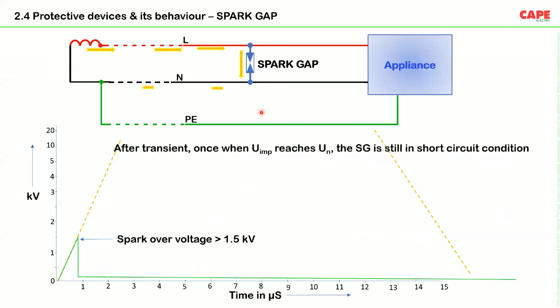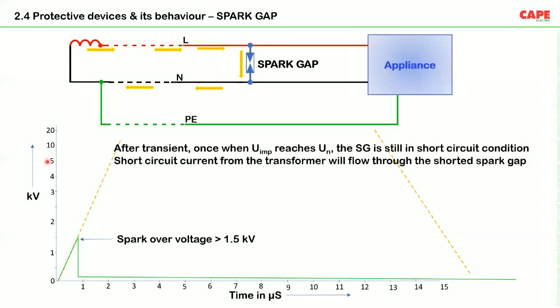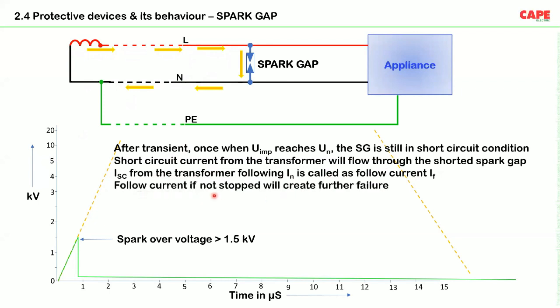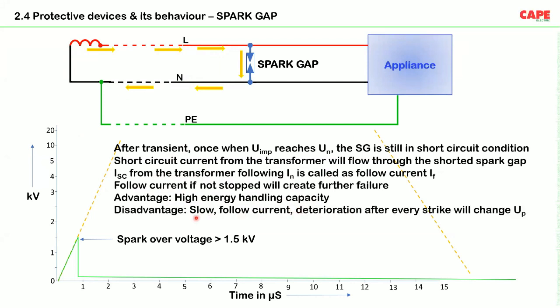As a result, the short circuit current of the network starts flowing through this device. This short circuit current, which follows the lightning current or the transient current, is called follow current. So short circuit current from the transformer will flow through the shorted spark gap. If this current flows for a longer time, we are in trouble. If the follow current is not stopped, it will create further failure. The advantage of a spark gap is it can handle high energy, whereas the disadvantage is it is slow. It has a parameter called follow current. It will also deteriorate after every strike.